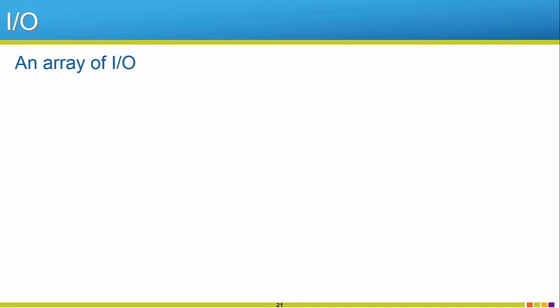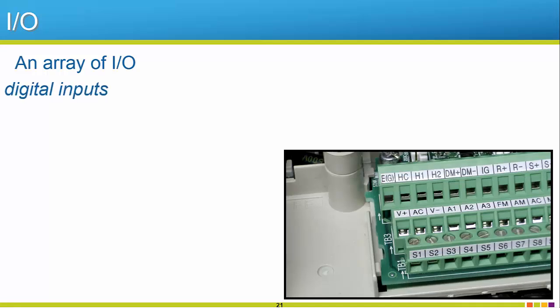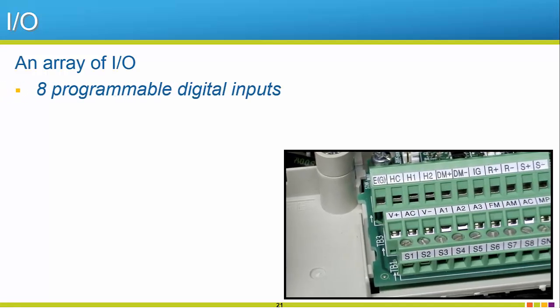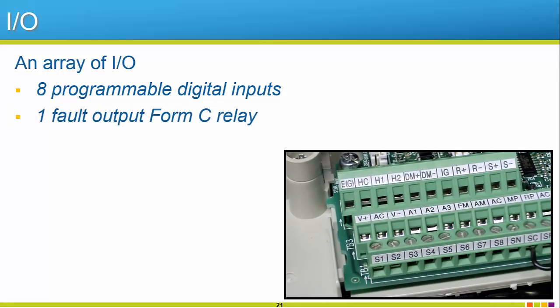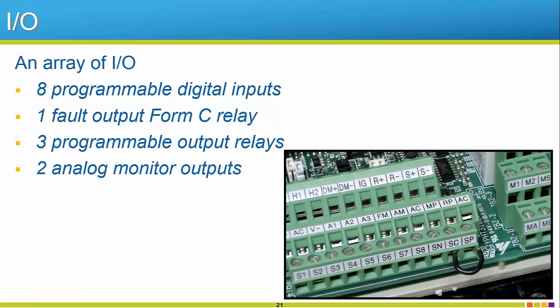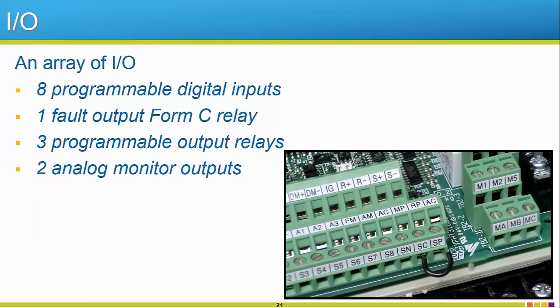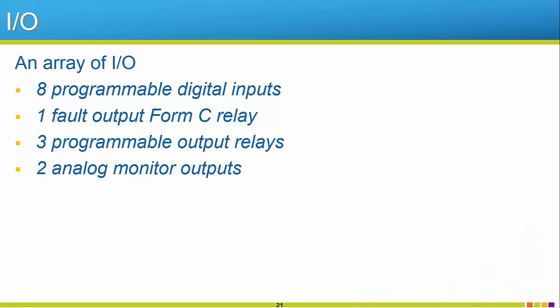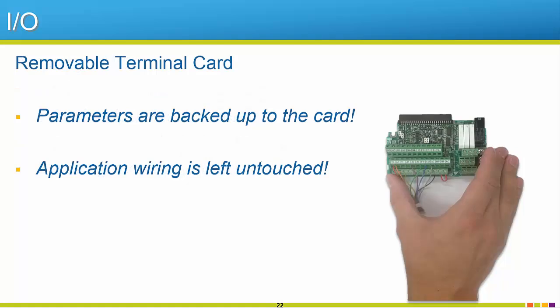The R1000 has plenty of IO to go around. Standard on all R1000s are 8 programmable, optically isolated, digital inputs. There's also one designated fault contact, which operates on a Form C relay, and 3 additional programmable contacts, which are Form A relays. Lastly, there are two programmable analog output monitors, which can source 0-10 volts or 4-20 milliamps. All of this robustness that is the R1000s IO is located on the removable terminal card. The removable terminal card is beneficial as it automatically backs up any programming changes to the unit. In addition to all the programming being backed up, your wiring is also stored on here. So unit replacement will fly by in no time, minimizing application downtime since all the wiring does not need to be re-landed and the parameters are already backed up.